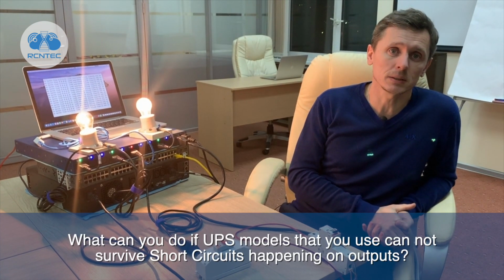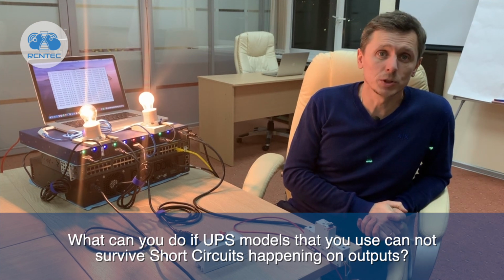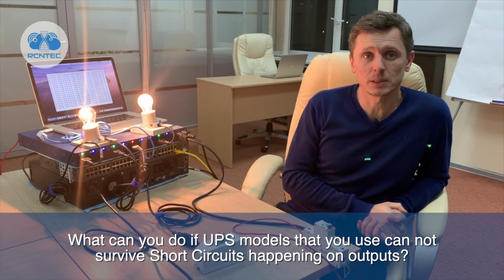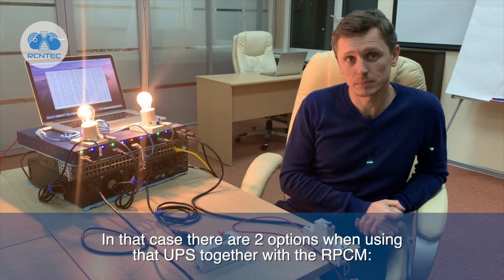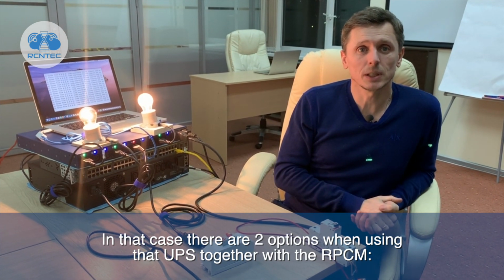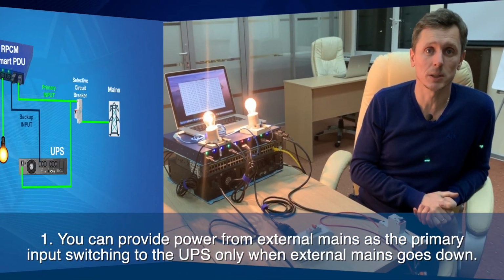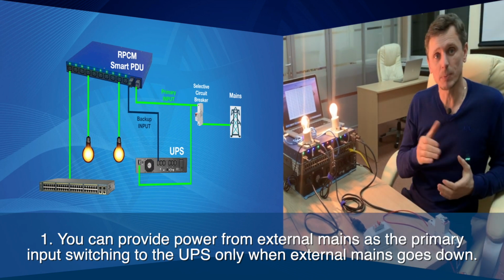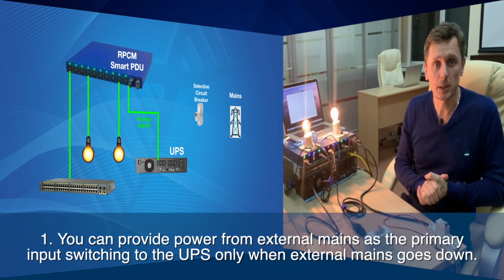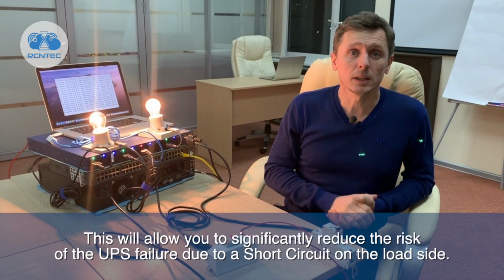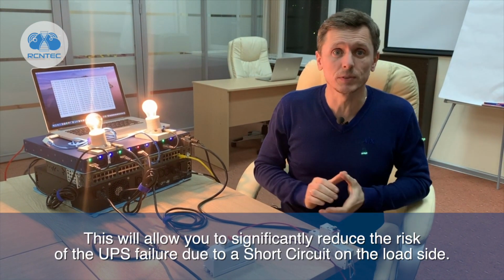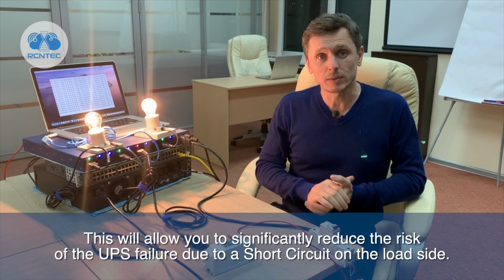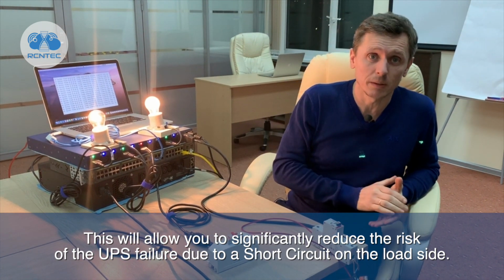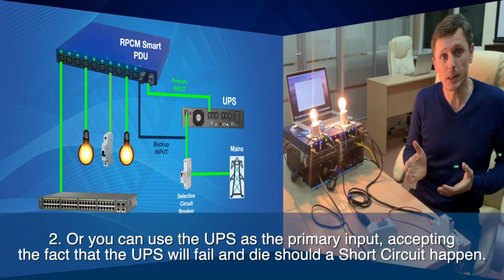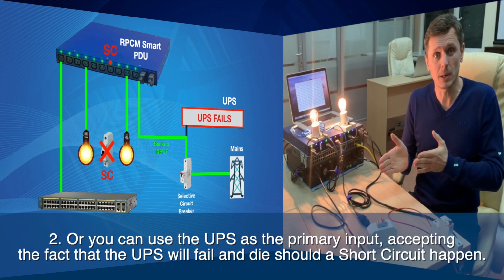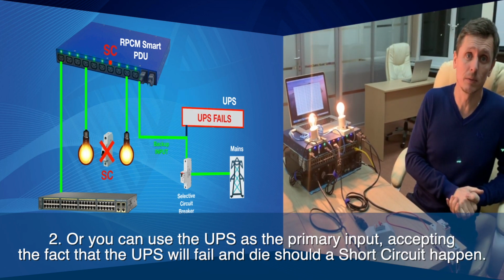equipment. What can you do if UPS models that you use cannot survive short circuits happening on outputs? In that case, there are two options when using that UPS together with the RPCM. You can provide power from external mains as the primary input, switching to the UPS only when external mains goes down. This will allow you to significantly reduce the risk of the UPS failure due to a short circuit on the load side. Or you can use the UPS as the primary input, accepting the fact that the UPS will fail and die should a short circuit happen.